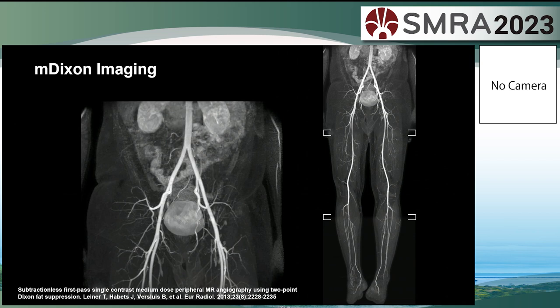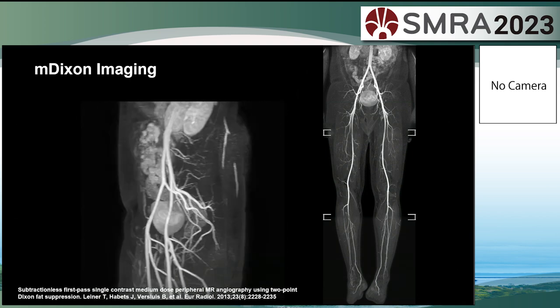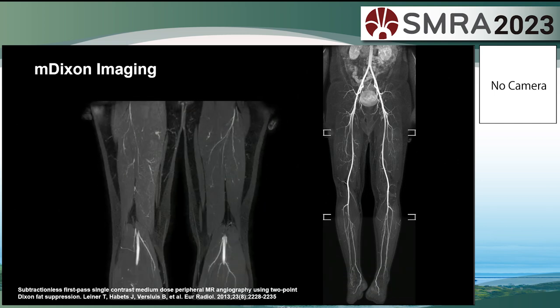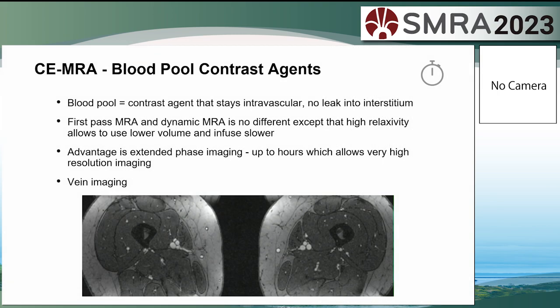Dixon imaging has been introduced for contrast-enhanced MRA — a paper from Tim Leiner with examples from my own practice. It provides intrinsic fat saturation, so we don't need to acquire a non-contrast volume to subtract from our contrast volume. We can go straight to acquiring the contrast-enhanced study.